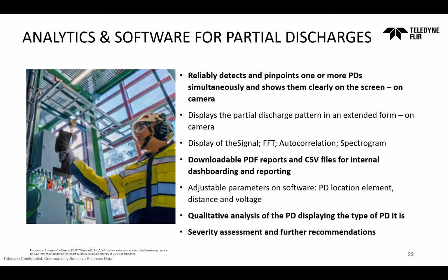That's fundamental. If you are not so familiar with the components, when you find a partial discharge, I always recommend you ask the customer you're visiting, because they need to know what every one of the elements is. If you have a PD somewhere in a substation and you don't know exactly the name of the component, please ask the customer; they should know. Of course, you can do it in a way that doesn't reveal that you don't know. But I'm just saying, if you don't know the name, please ask about it, because it will help you give really good reporting to the customer.